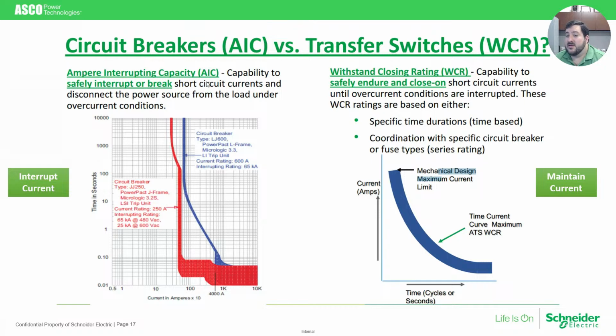Additionally, it must also be rated to close onto a fault scenario. So again, the ATS is going to survive it and withstand it. The circuit breaker is going to interrupt it. So the requirements in the design of these products are very different, because one has to survive it for an extended period of time, while the other one has to interrupt it, and it has different characteristics that go into the design consideration between those two things. So do not confuse the KAIC rating of a breaker with the WCR rating of a transfer switch. That's the main message there.